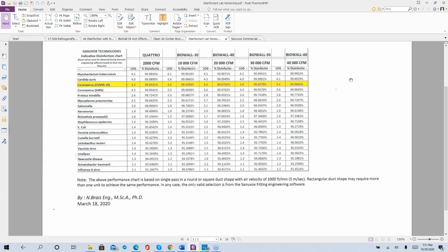So one of the things that we do in order to get to that high kill rate is that we actually include a 4-foot section of aluminum duct to mount the UV in the shop with an access door and a safety switch and an airflow switch to interlock the UV with the airflow. We then remove the existing 4 feet of sheet metal duct and install the new aluminum 4 feet back into the duct system.